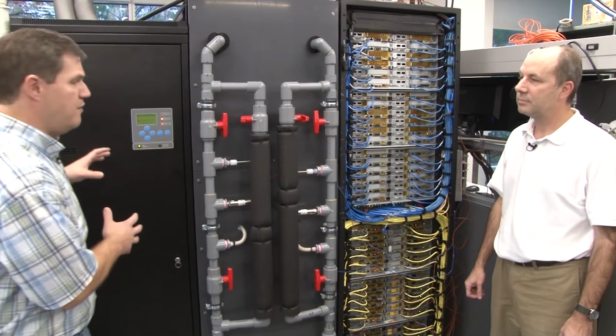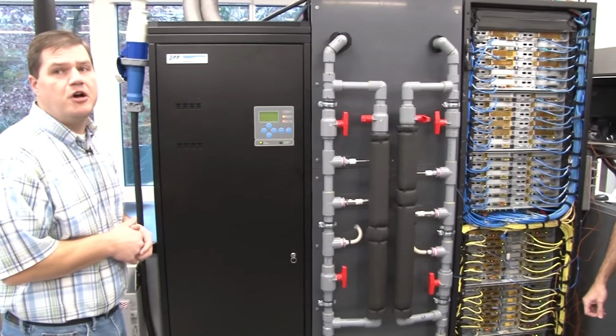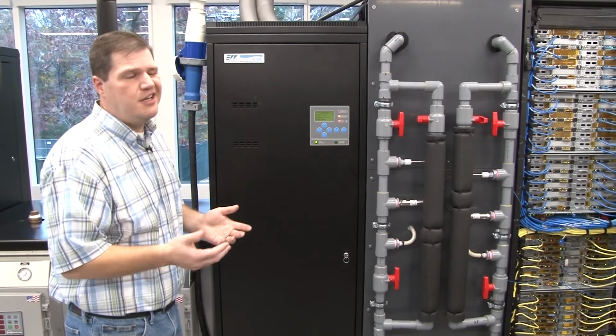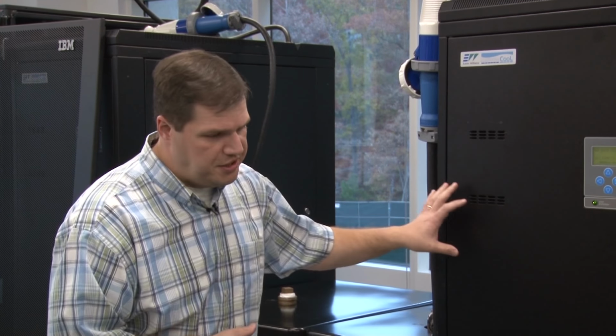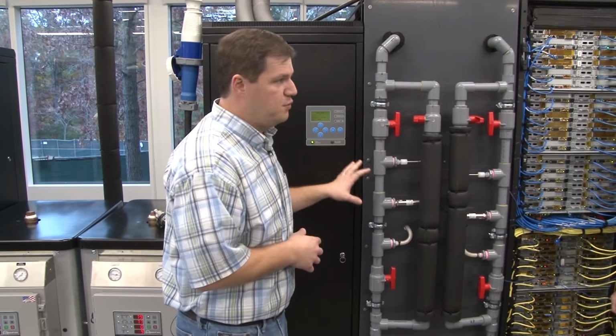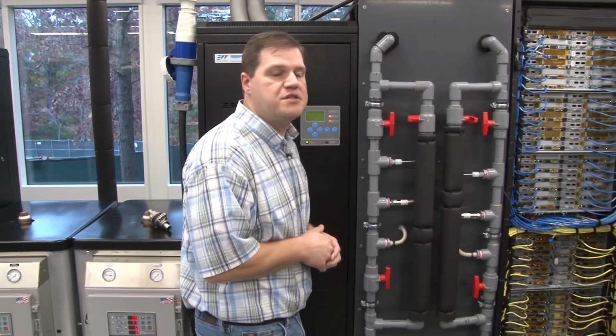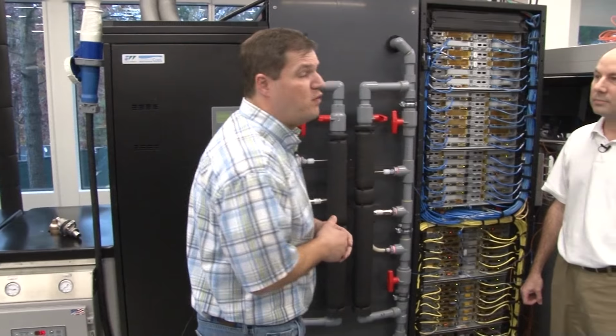And then I have over here a CDU. This is a pretty common CDU that you would see in industry and in customer applications. So our CDU on the secondary side is feeding my test rack through the instrumentation so we can make measurements and determine the thermal performance of the rack.